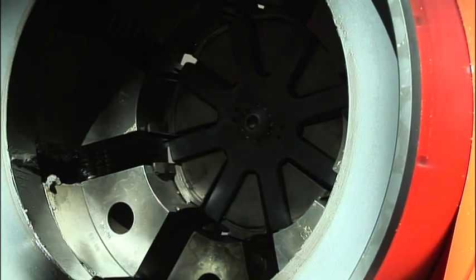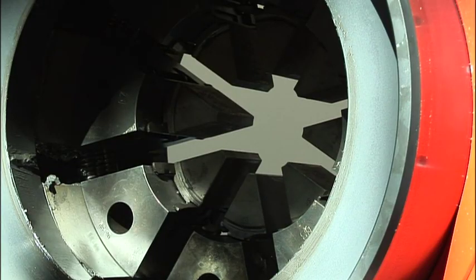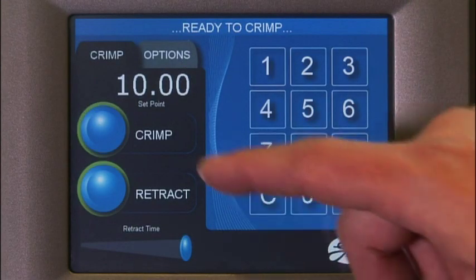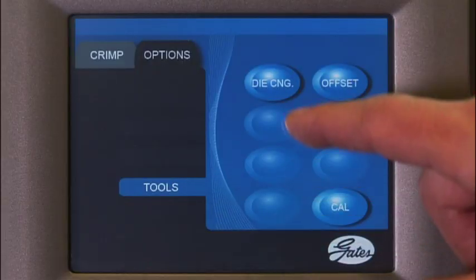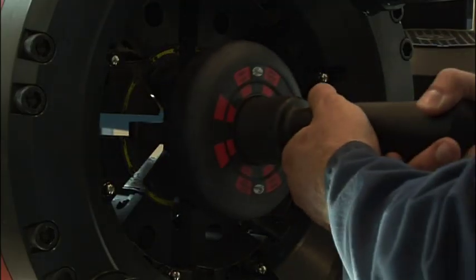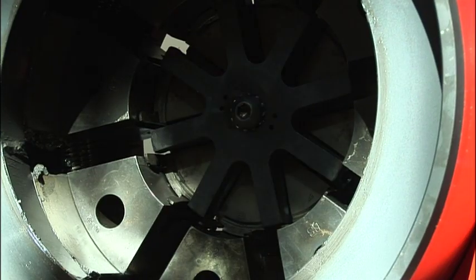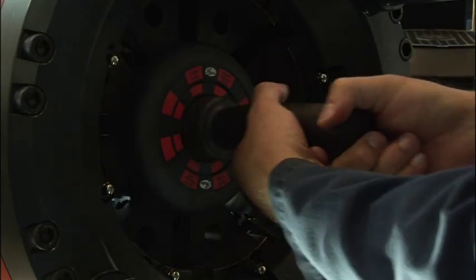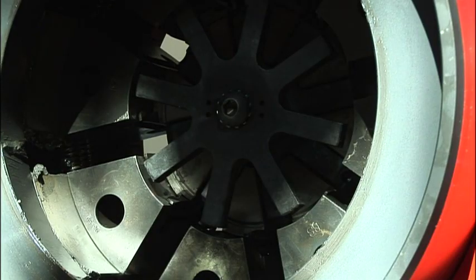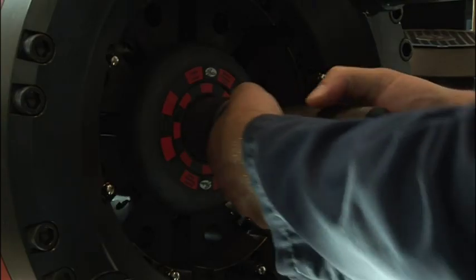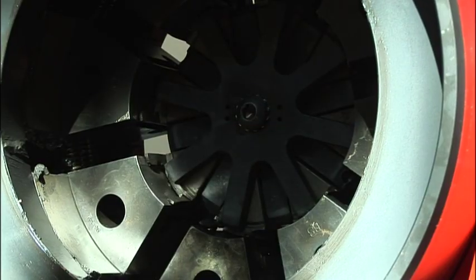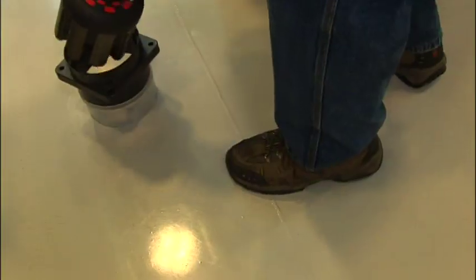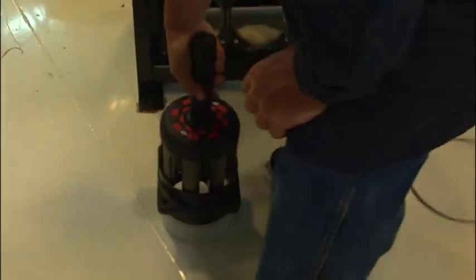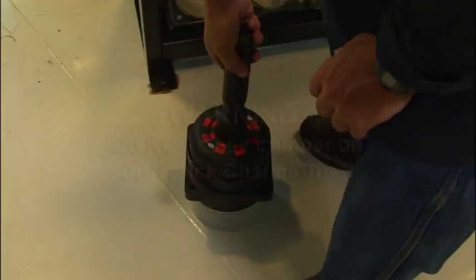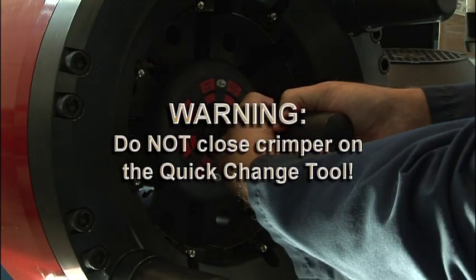To uninstall the GC32 standard die sets, position the head as before by pressing the Options tab, then the Tools tab, then the Die Change button. Slide the Quick Change tool in until it bottoms out on the die shoe surface. Twist the Quick Change tool to the right or clockwise until the die segments are engaged, and then pull the Quick Change tool straight out. This will pull the die segments out of the crimper head. Place the GC32 die segments back into the storage receptacle. Warning: closing the crimper head on the Quick Change tool will damage the Quick Change tool.